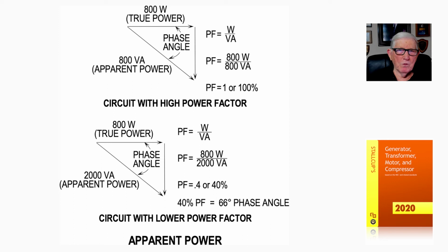You take in Fort Worth, if they haven't changed it, the utility required 95% power factor. And engineers had to see to it that they got that, or the utility would put in condenser banks to raise that power factor up to that value or higher, and would charge monthly for those condenser banks, or the engineer would have to do that. So they would have to prepare in such a way to correct poor power factor. And that's what this figure 14-16 is showing, how to determine the power factor is illustrated.